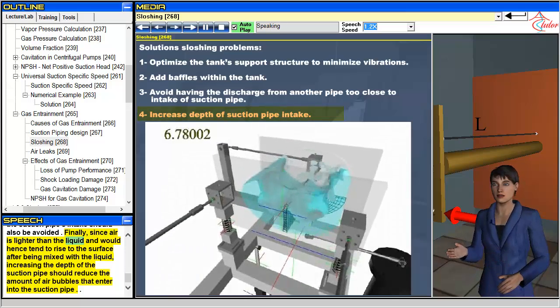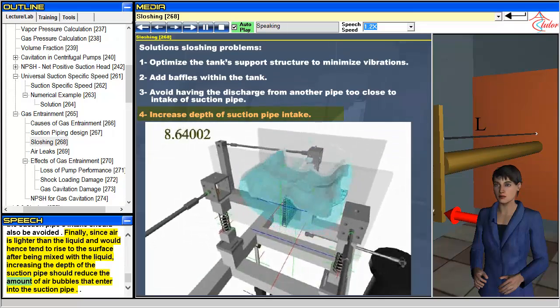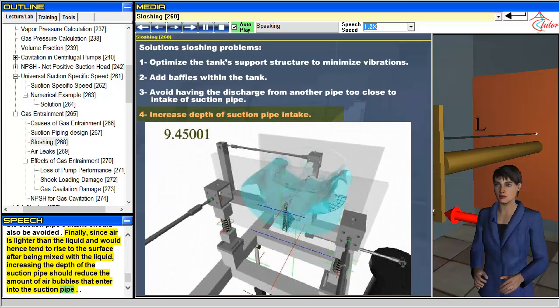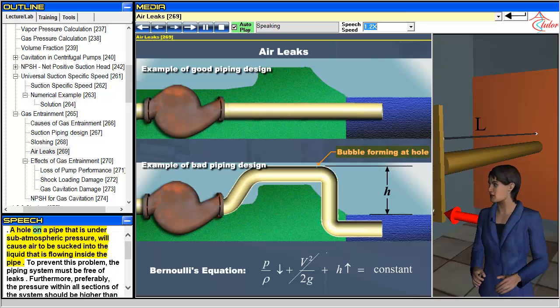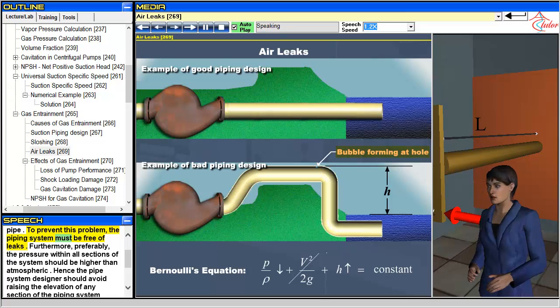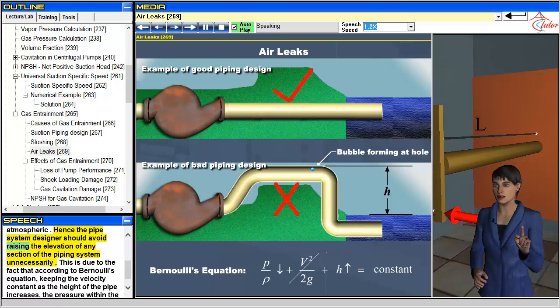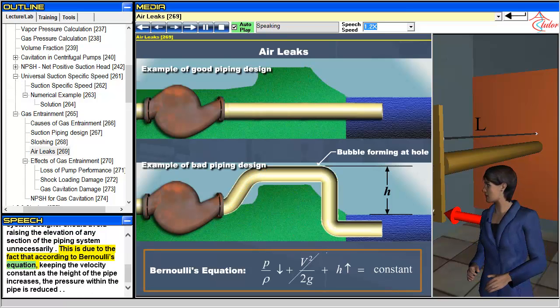Finally, since air is lighter than the liquid and would tend to rise to the surface after being mixed with the liquid, increasing the depth of the suction pipe should reduce the amount of air bubbles that enter the suction pipe. A hole on a pipe that is under sub-atmospheric pressure will cause air to be sucked into the liquid flowing inside the pipe. To prevent this problem, the piping system must be free of leaks, and preferably the pressure within all sections of the system should be higher than atmospheric. Hence the pipe system designer should avoid raising the elevation of any section of the piping system unnecessarily, since according to Bernoulli's equation, keeping the velocity constant, as the height of the pipe increases, the pressure within the pipe is reduced.